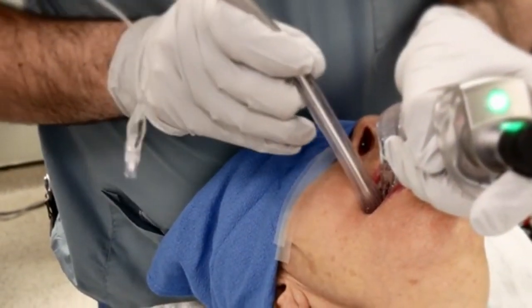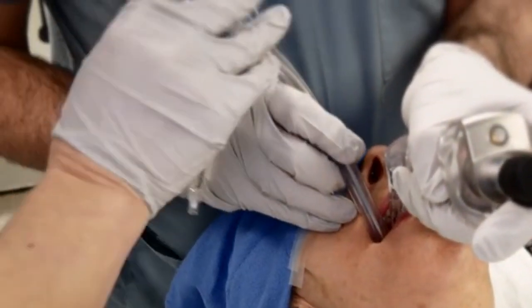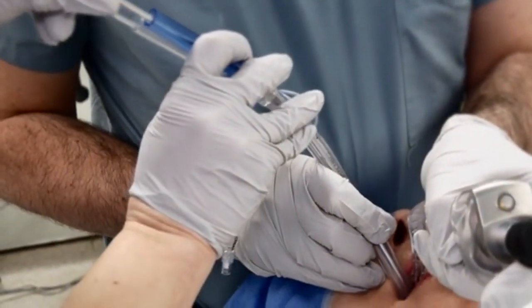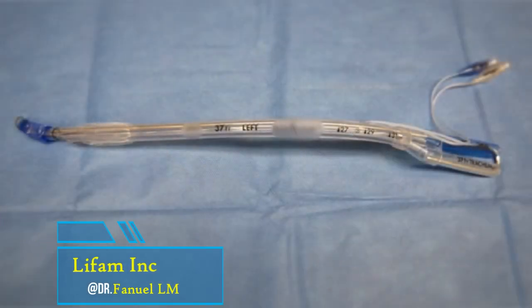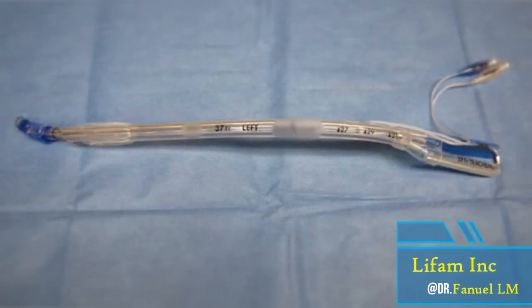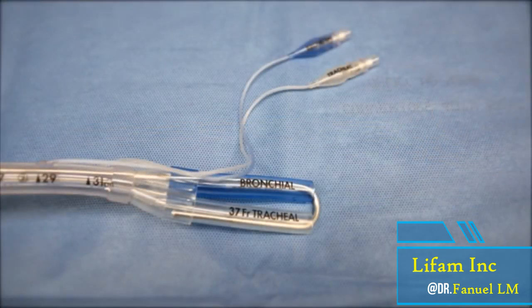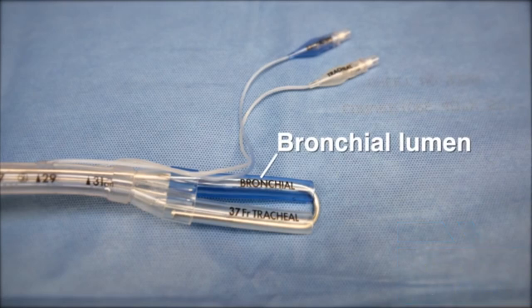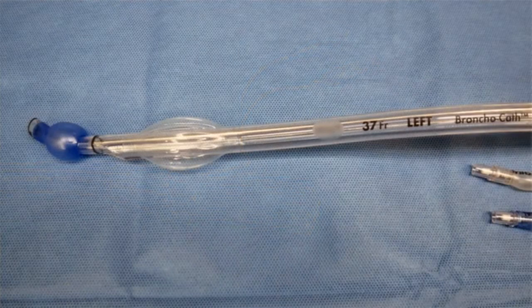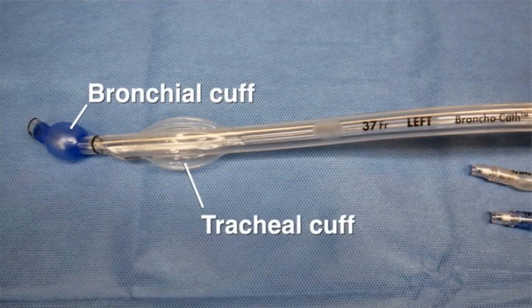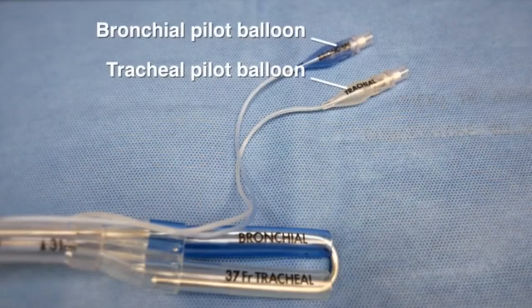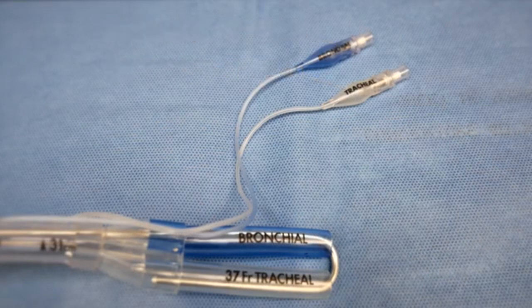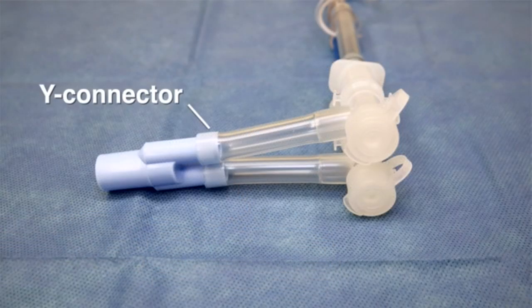Placement of a double lumen endotracheal tube is an airway management technique that permits isolation and selective ventilation of a single lung. Double lumen endotracheal tubes consist of a bronchial lumen and a tracheal lumen. The bronchial lumen is longer with a distal opening designed to be placed in the right or left main stem bronchus. The tracheal lumen is designed to be placed above the carina. Each lumen has a color-coded cuff, often blue on the bronchial lumen and clear on the tracheal lumen, as well as a color-coded pilot balloon. A Y connector connects both lumens to the breathing circuit.